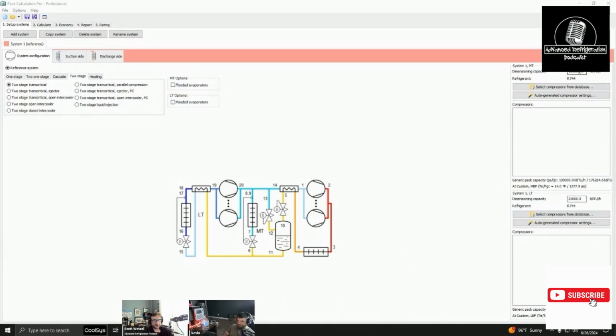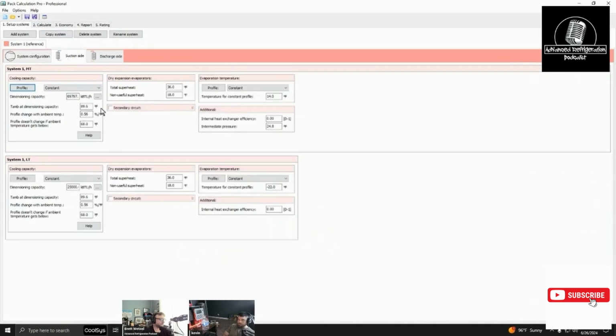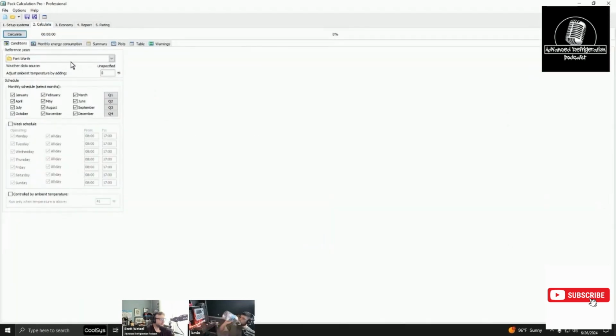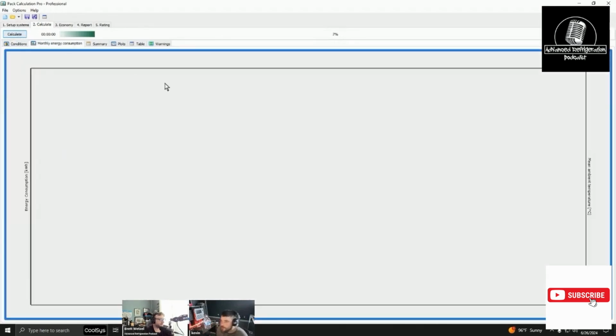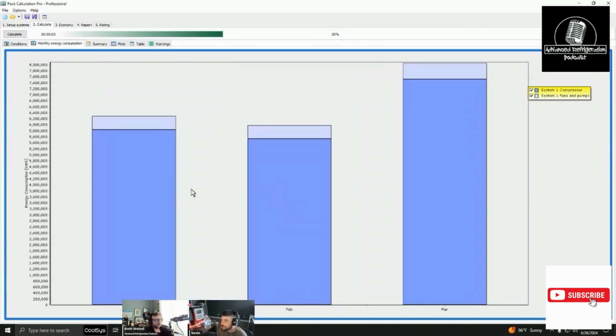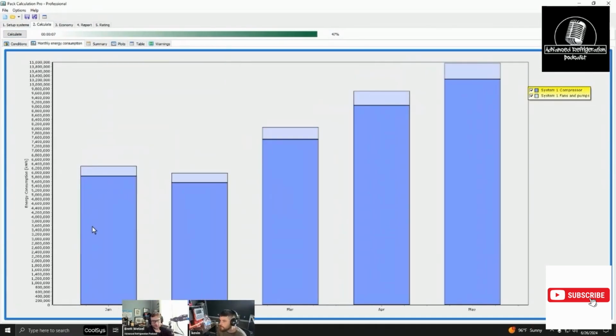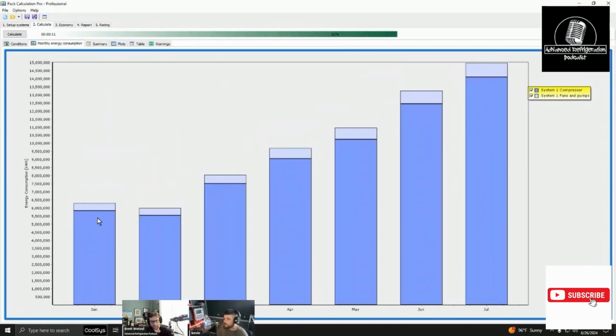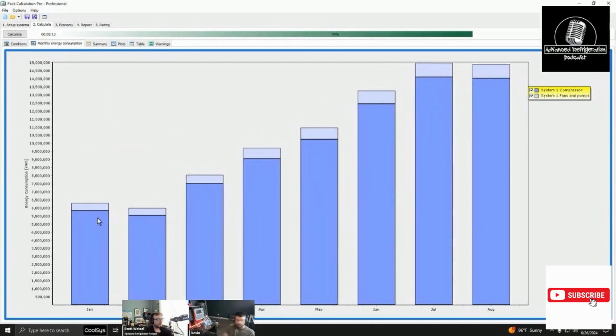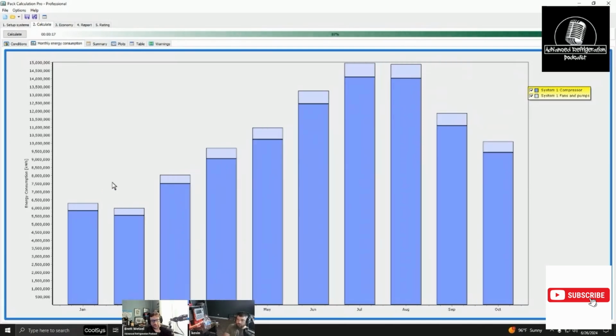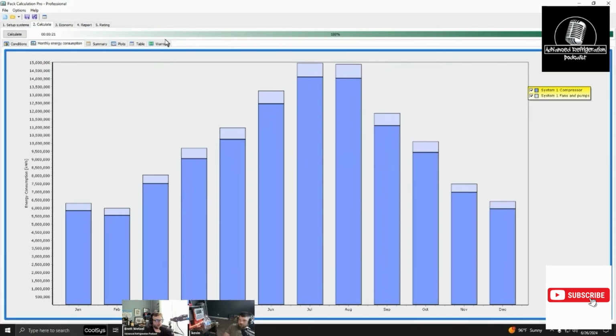Every time I try to size something — so I have 100,000 BTUs here, and on the low temp I have 25,000. On this software you have your heat exchangers and all this other information, same thing with the discharge side. I calculated it for what the saturation temperature would be out in Fort Worth, and when I hit calculate we'll see what happens. Based off the temperatures, it's actually pretty rad — it'll figure out the energy consumption depending on what compressors it picks. But if I have anything messed up or didn't size something properly, it yells at me and gives me a warning, and then I have to try again.